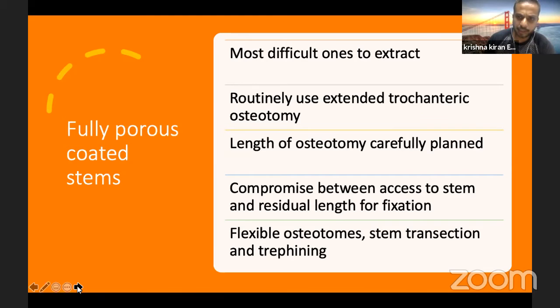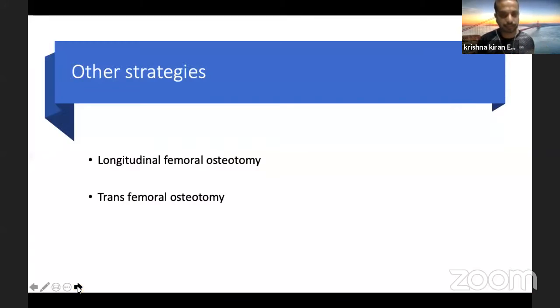There is always a compromise between access to the stem and residual remaining length of bone for fixation of the revision implant. So this must be tailored individually, and you must be prepared with stem transection devices. So you must have metal cutting burrs and trephines. So you have 12, 14, 16 hollow mill type of trephines available in the revision set. So you can transect the stem, remove that stem at the level of the osteotomy if it is too long, and then the remaining part of the stem can be removed by using these trephines passed over the top of the remaining cylindrical part of the stem.